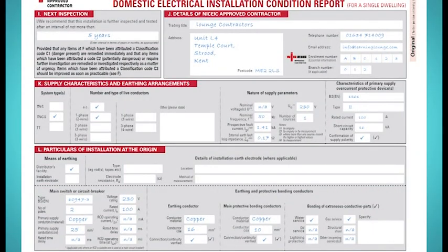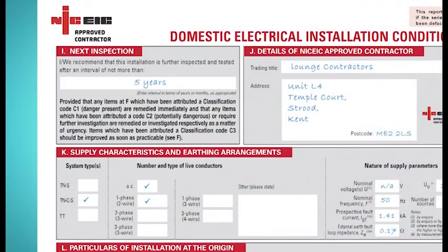With regards to the supply characteristics and earthing arrangements, this was fairly straightforward for our installation. But don't forget, for a property with backup or alternative supplies, it will be necessary to provide the supply parameters information for these as well. We've also got a box to write down the date of the next inspection. So what are you going to put down, Tone? Well, like I said on site, although the insulation resistance values pass those required by the regs, they aren't as good as I would like to see for a property of this age. So after due consideration, I'm going to reduce the period to the next inspection to 5 years rather than 10.